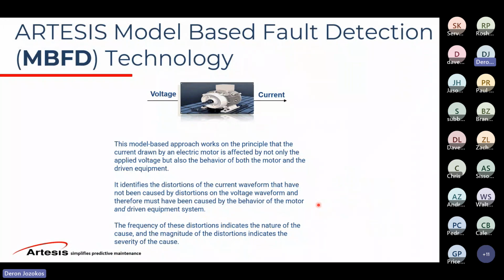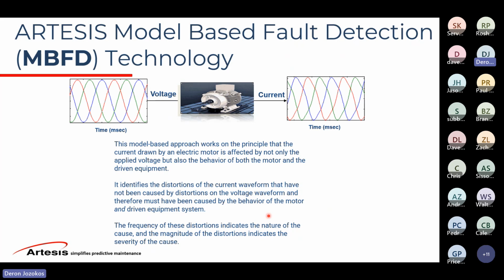So this model-based approach works on the principle that the current drawn by an electric motor is affected by not only the applied voltage, but also the behavior of both the motor and driven equipment. It identifies the distortions of the current waveform that have not been caused by the distortions on the voltage waveform, and therefore must have been caused by the machinery itself, the components of the machinery, the defects. The frequency of these distortions indicates the nature, so similar to vibration, the frequency tells us what the cause of it is, and the magnitude, amplitude, tells us the severity.